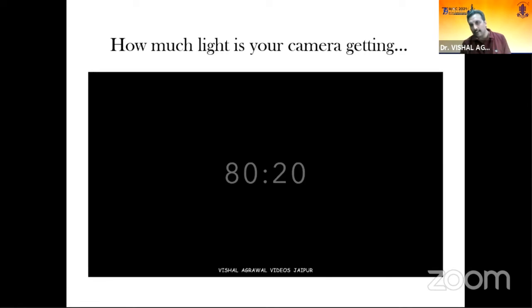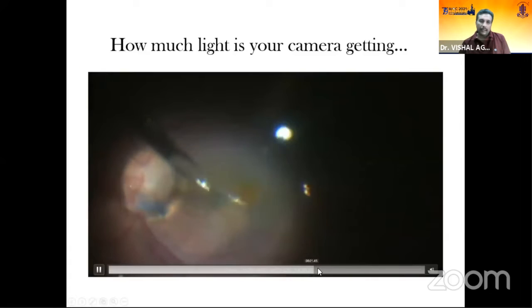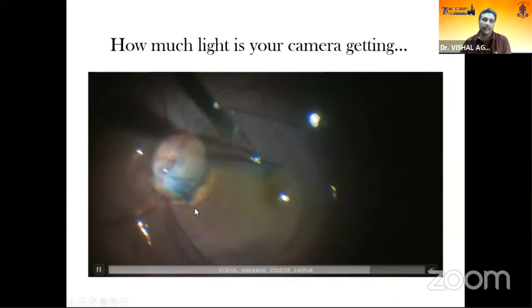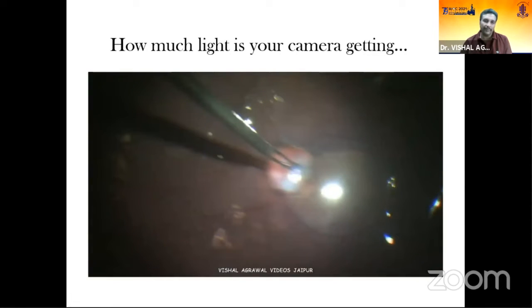How much light your camera is getting is very important, which is why you should know the details of your beam splitter. Previously most beam splitters from Zeiss came in 50/50 — meaning 50% of light reached you and 50% to the camera. Newer models are 80/20. In a 50/50 setup with an optic disc pit case in a pediatric patient, I had to increase illumination for optimal recording. With an 80/20 beam splitter, another optic disc patient came through clearly without any adjustment to illumination or brightness.